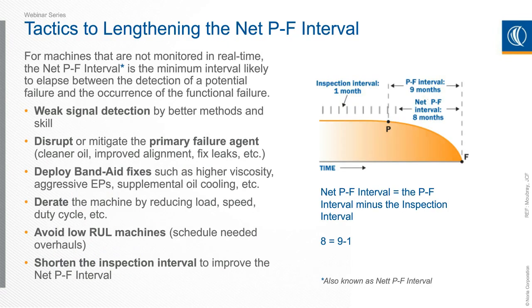RCM refers to something that's called the net PF interval. The net PF interval is the PF interval minus the inspection interval, the time between inspections or condition monitoring. For machines that are not monitored in real time, the PF interval is the minimum interval likely to elapse between the detection of a potential failure or fault and the occurrence of that functional failure. So how do we lengthen that? What are our strategies for that?